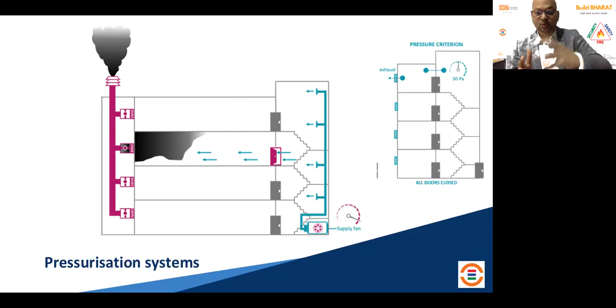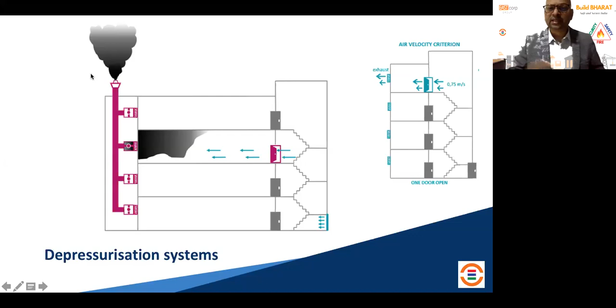Depressurization, again you are going to do the same thing, but there is no supply here. It's only exhaust which is on. Vis-a-vis in pressurization, you have a supply fan here. So that means mechanically you are injecting fresh air to restrict the smoke from entering from the area which is under fire. Vis-a-vis in depressurization, we are not injecting any air. We are just turning the exhaust on, and we are expecting the smoke to go out.